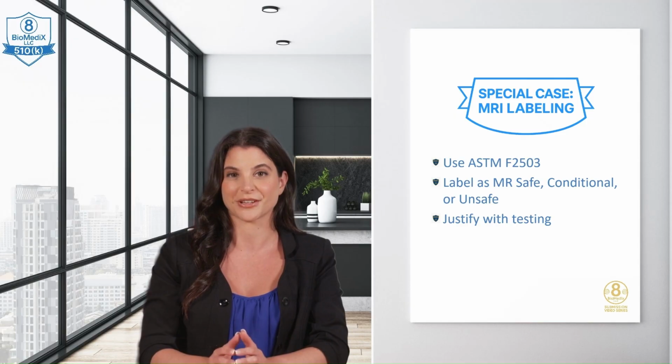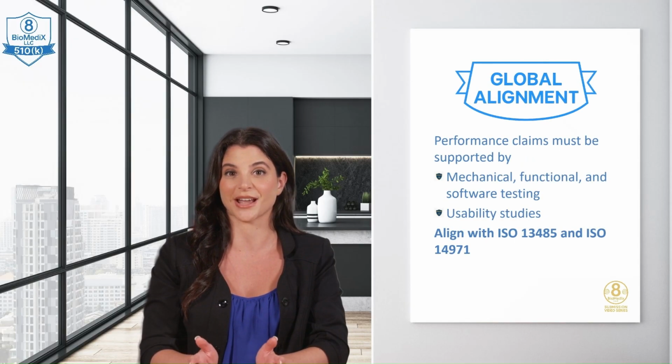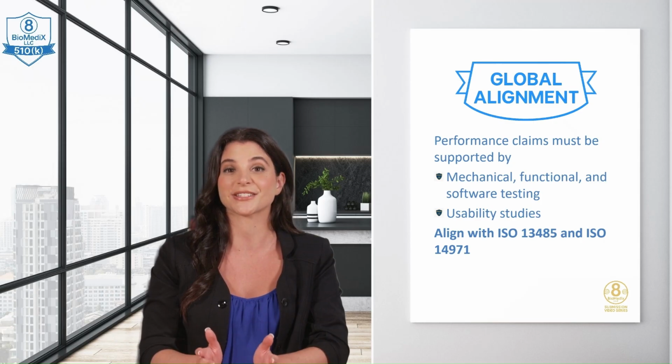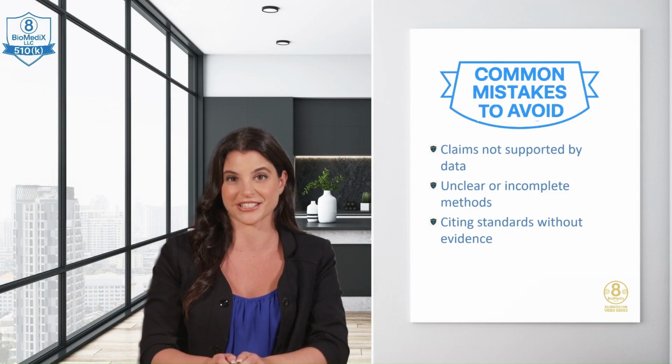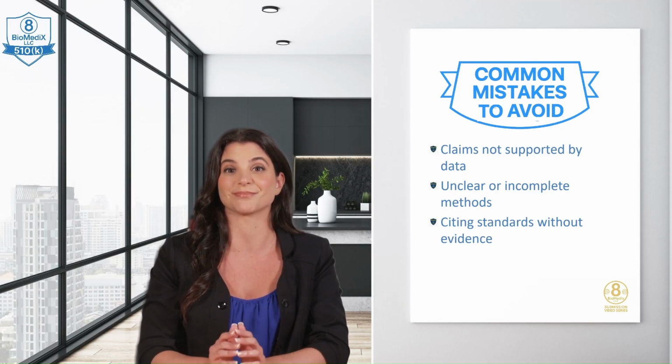Performance claims and global alignment. Every performance claim must be backed by test data. For international markets, especially EU MDR compliance, this includes mechanical performance, functional and software validation, and usability studies. Standards like ISO 13485 and ISO 14971 also require that testing supports risk controls and doesn't introduce new risks. While eSTAR is for FDA, aligning your testing with international standards strengthens your entire submission.